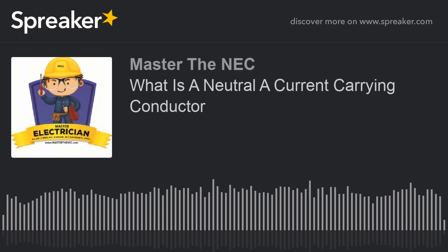Now, another example of this would be a pure multi-wire branch circuit, where we're dealing with an NMB, which is, just for argument's sake, a 14-3 with a ground. So I have a black, a red, a white, and a bare equipment grounding conductor. And it's going out to, and it's in a panel, and it has a 2-pole breaker or 2 single-pole breakers with an identified handle tie. The whole concept is to keep them side by side so that one side of that breaker is being fed from phase A, and the other of that 2-pole breaker is being fed from phase B, so that we can take advantage of that cancellation.